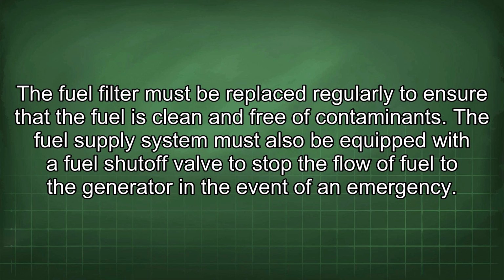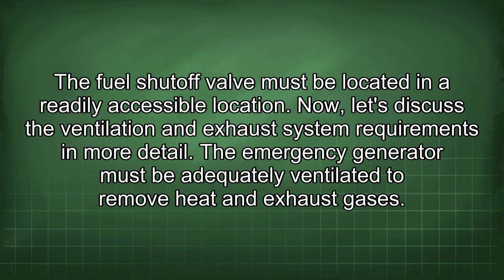The fuel supply system must also be equipped with a fuel shutoff valve to stop the flow of fuel to the generator in the event of an emergency. The fuel shutoff valve must be located in a readily accessible location.